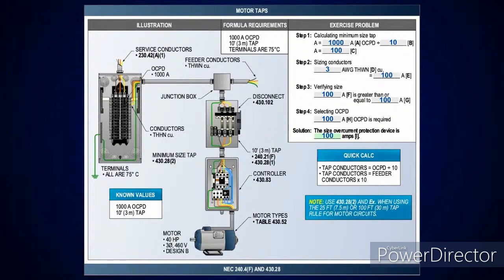Now here's a tap, and I've got a 10-foot tap here. I've said this before: if it's 10 feet or less, what do we divide by? 10. So my upstream overcurrent device is 1,000 amps. I take the 1,000 amps divided by 10, which gives me 100. Then if I look at table 310.16 in the 75 degree C column, the number 3 is good for 100 amps. So the overcurrent device and conductor match up. Therefore you would need a 100 amp overcurrent protection device with number 3 conductors.